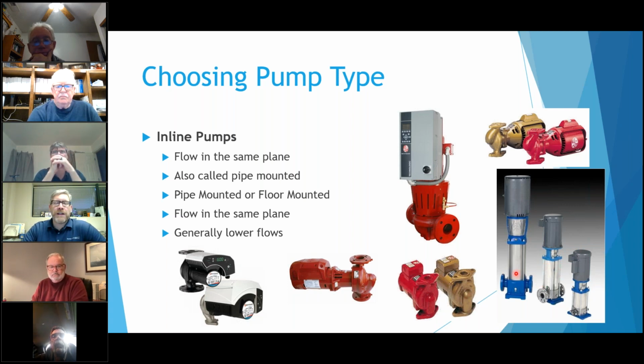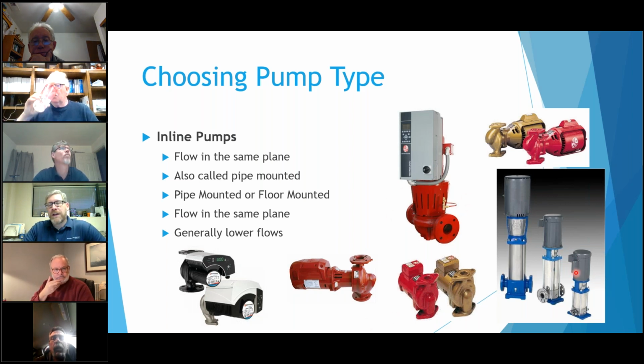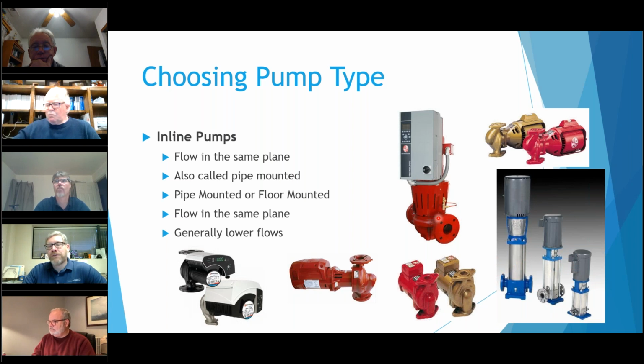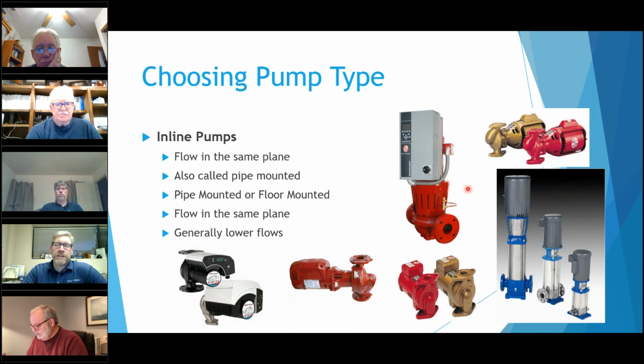They're also called pipe mounted pumps, because they are mounted right in the pipe. I want to point out though, especially this one here, as well as these, they will also be mounted on the floor because they can get quite large. But for the most part, the pipe is supporting the pump itself. And as you can see, with inline the flow's in the same plane. It comes in one side, out the other. But they're usually used on smaller systems or smaller types of systems.